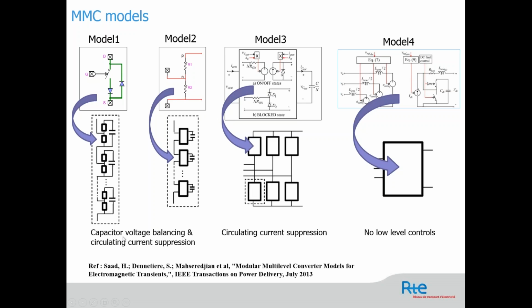Models 1 and 2 can represent the capacitor voltage balancing, since the submodules are represented. So the capacitor voltage balancing control should be used to balance all the capacitors, along with the circulating current suppression. In model 3, since the submodules are aggregated, the capacitor voltage balancing is not used because the capacitor is already simplified, but the circulating current suppression should still be used. For model 4, you don't have any lower level control. You just need a representation of the outer control or the inner control.